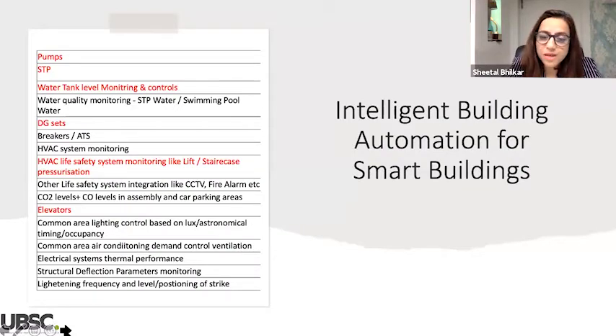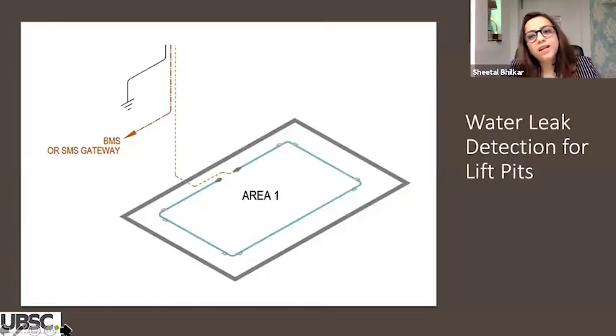Then of course BMS is designed for all the high rises, where all preventive maintenance and maintenance schedules you get on your mobile. So you get pumps, STP, DG set, all these maintenance schedules at your fingertips. So this we have to do for all the high rises. If you do preventive maintenance properly, then you don't get many maintenance problems. Then again, water leak detection you have to suggest for lift pits.